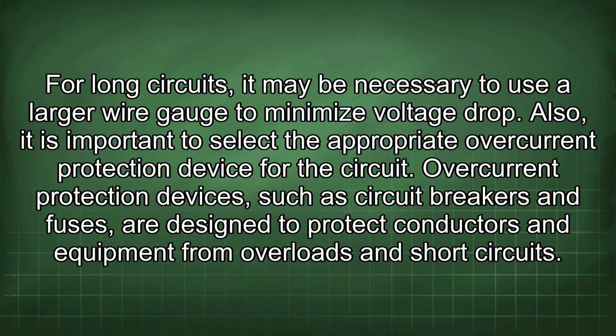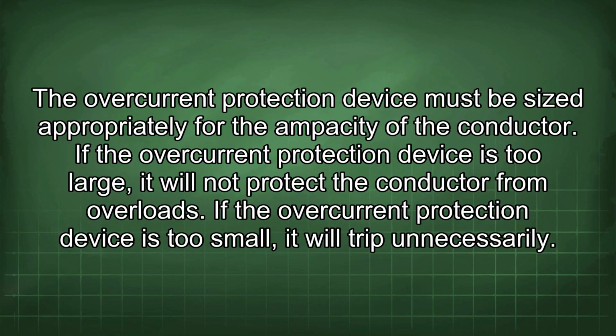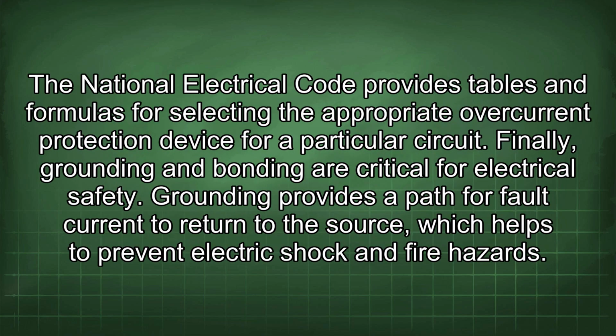Also, it is important to select the appropriate overcurrent protection device for the circuit. Overcurrent protection devices, such as circuit breakers and fuses, are designed to protect conductors and equipment from overloads and short circuits. The overcurrent protection device must be sized appropriately for the ampacity of the conductor. If the overcurrent protection device is too large, it will not protect the conductor from overloads. If the overcurrent protection device is too small, it will trip unnecessarily. The National Electrical Code provides tables and formulas for selecting the appropriate overcurrent protection device for a particular circuit.